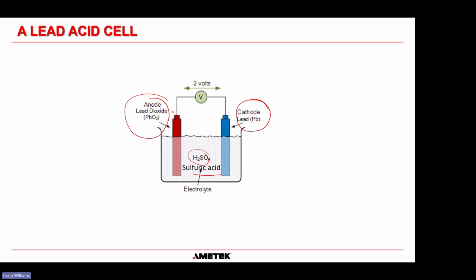If you put a lead dioxide plate in this tub, and a lead plate in this tub, fill the tub with sulfuric acid, and put a multimeter across the positive and negative posts, the nominal voltage of the lead acid cell would be 2 volts. Now, we'll go into why that's not exactly accurate in a little bit, but in the grand scheme of things, to make things easy, that's what the industry standard says.